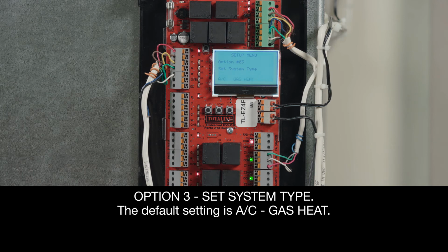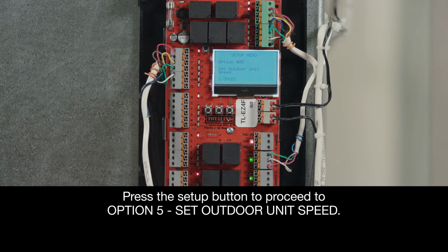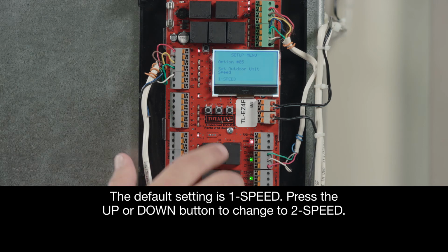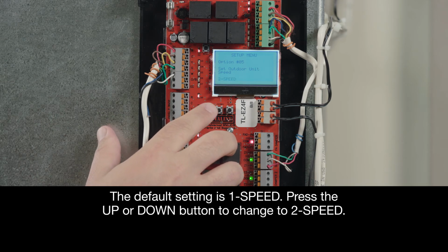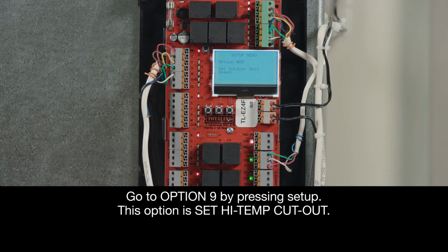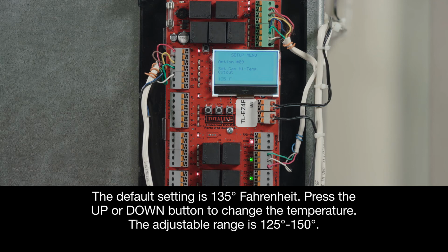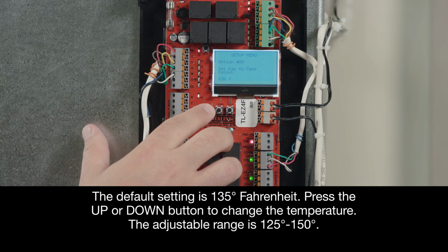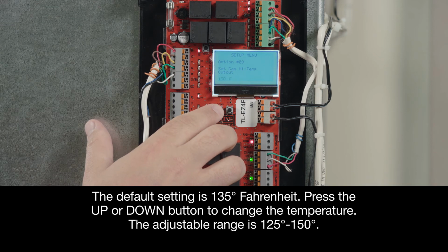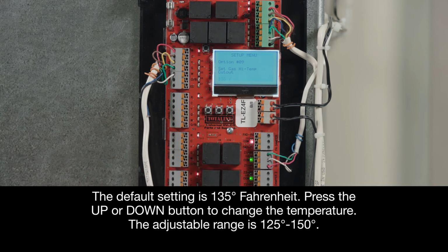Now we're on option 3, Set System Type. The default setting is AC gas heat. Next, press the Setup button to proceed to option 5, Set Outdoor Unit Speed. The default setting is 1 speed. Press the up or down button to change to 2 speed. Now let's go to option 9 by pressing Setup. You can see this option is Set High Temp Cutout. The default setting is 135 degrees Fahrenheit. Press the up or down button to change the temperature. The adjustable range is 125 to 150 degrees.